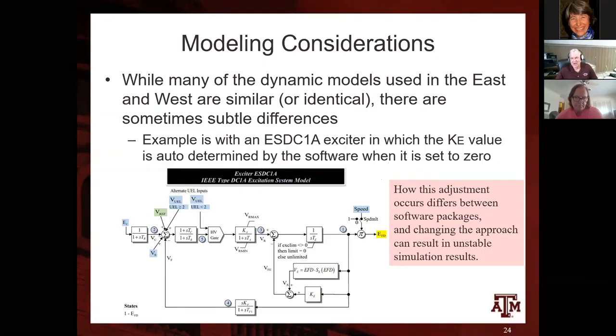This differs between what's done in the East versus the West—not that one side is correct and the other isn't, it's just that the models are tuned for different software modeling assumptions. When you put them together, if you don't use those same assumptions, you get oscillatory responses. So we had to address these issues, and we did.